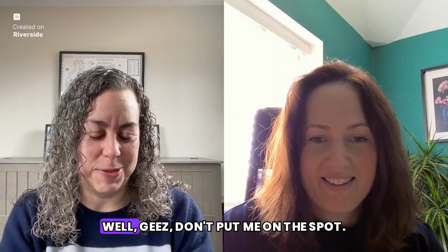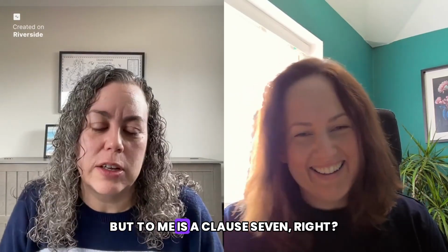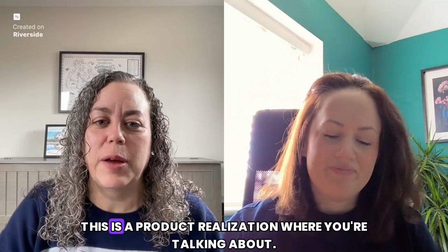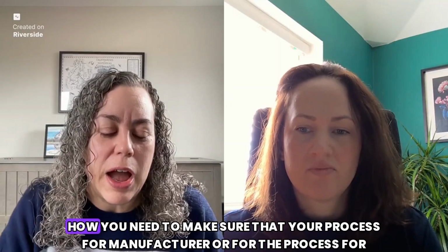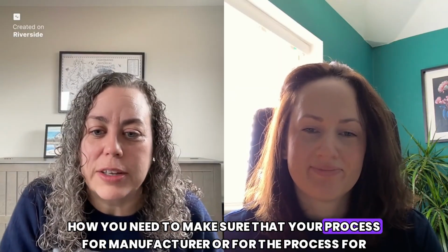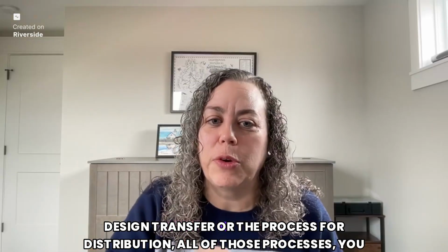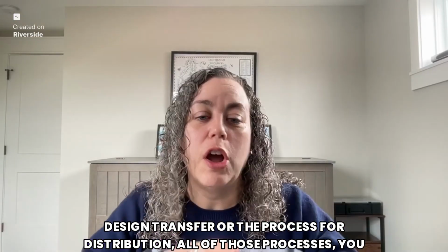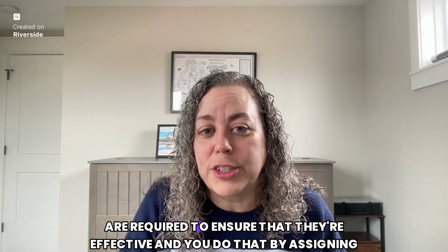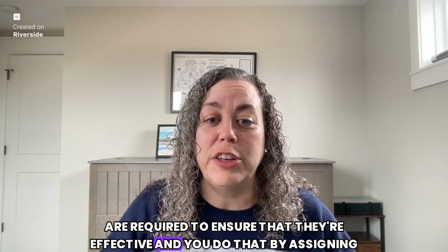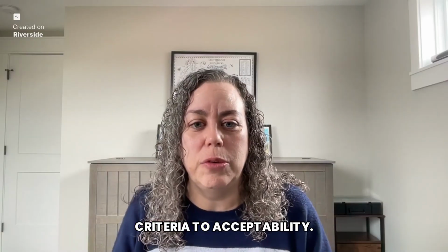Well, geez, not to put me on the spot, but to me it's clause 7, right? Product realization, where you need to make sure that your process for manufacture, or the process for design transfer, or the process for distribution, all of those processes you are required to ensure that they're effective, and you do that by assigning criteria for acceptability.